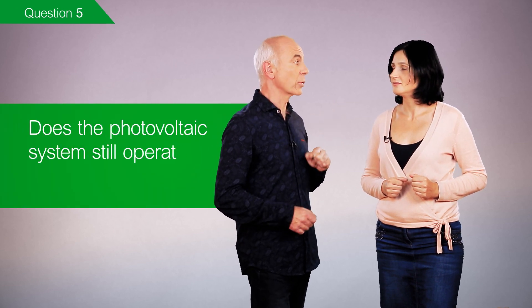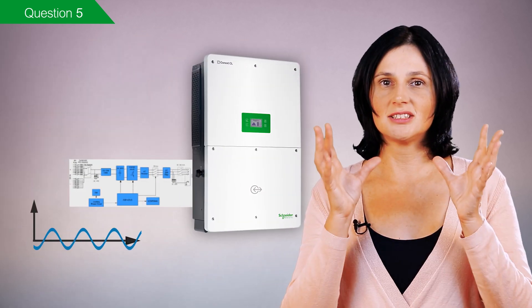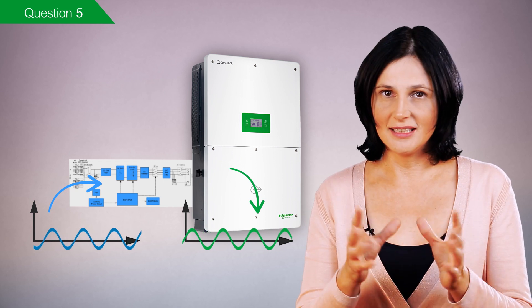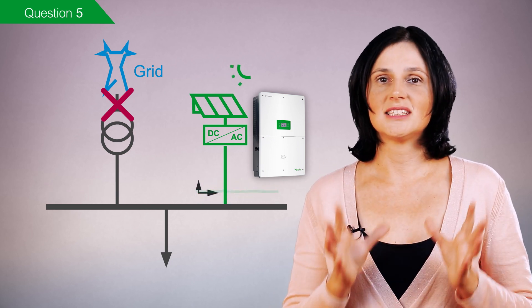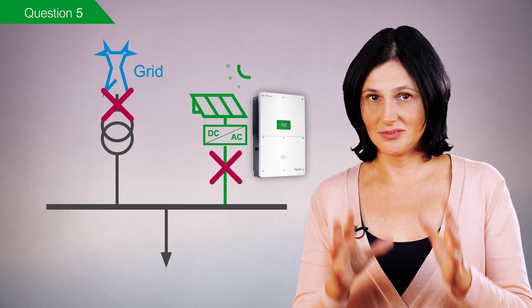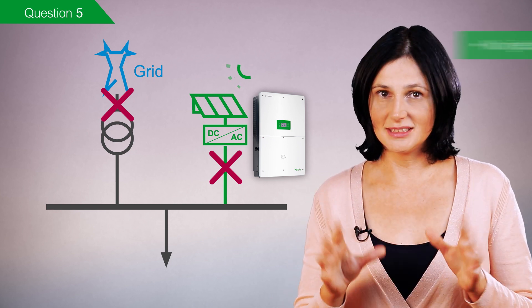One last question for today: does the photovoltaic system still operate during a grid outage? No. Grid-tied photovoltaic inverters need a source that delivers the voltage and frequency reference, such as the electrical grid. They are not designed to operate off-grid. In case of a grid outage, the solar inverters disconnect rapidly as the voltage in the electrical installation goes outside of the specified limits. This fast disconnection — less than one cycle — also guarantees that the inverters do not inject power into the grid, which is essential for the safety of utility workers.